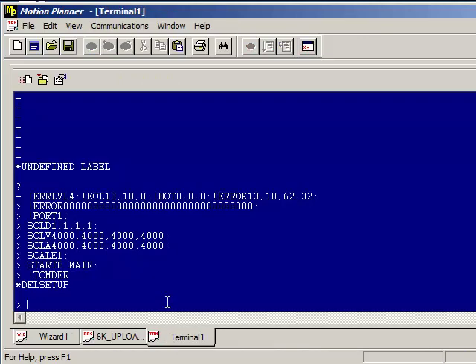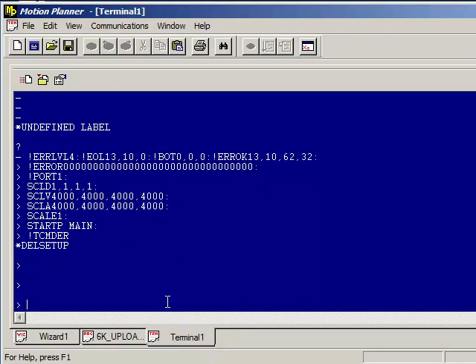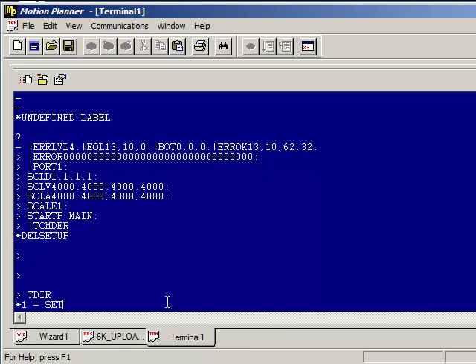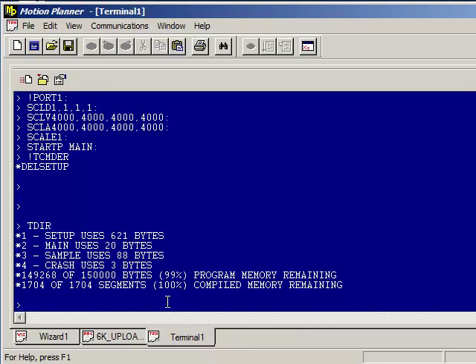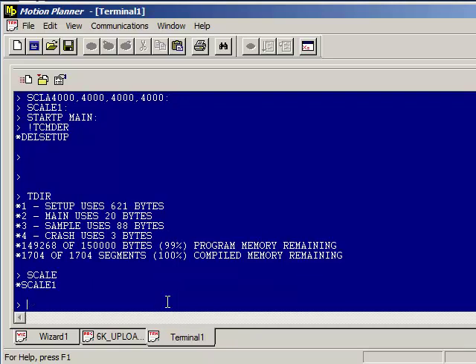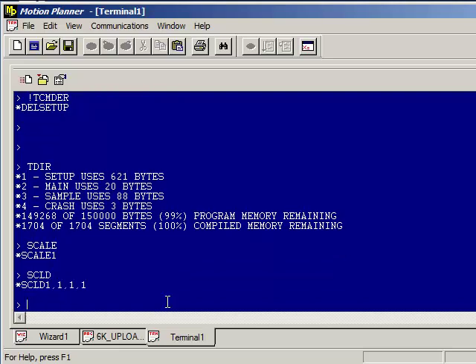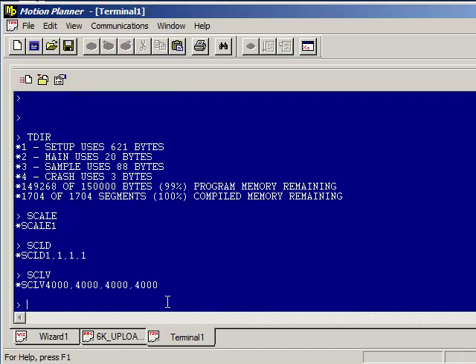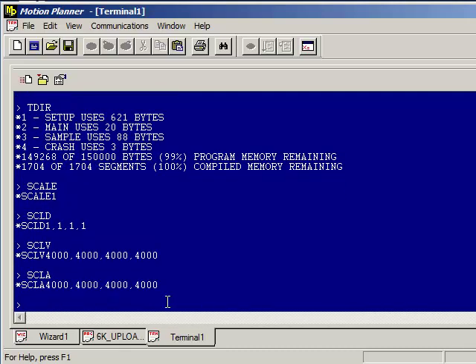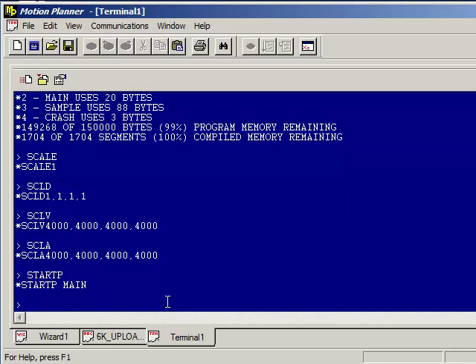In the terminal window, if you want to then verify the programs are there, you can type TDIR transfer directory. And you can see setup, main, sample, and crash are all defined within the 6K. Then if you want to verify the scaling parameters, you can type scale without any argument behind it. You can see that it has been set to 1 and set SCLD and SCLV and SCLA. You can see those all match. And then if you type start P without the argument, you can see it is set to main.